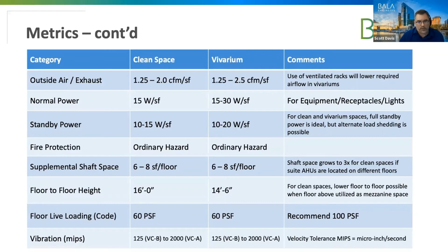More so if you're utilizing ventilated racks for the rodents as well, because in the case where you have ventilated racks, your typical room might be, say, an air change rate anywhere between 8, and I've seen them as high as 15 air changes. And again, that's for odor control. But if you have ventilated racks, that required high air change rate is really isolated to just the racks themselves. So you can have a significant decrease in air.